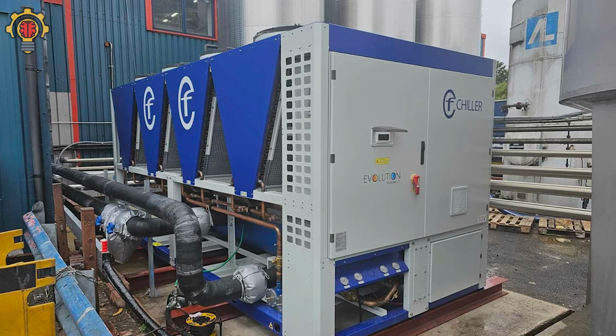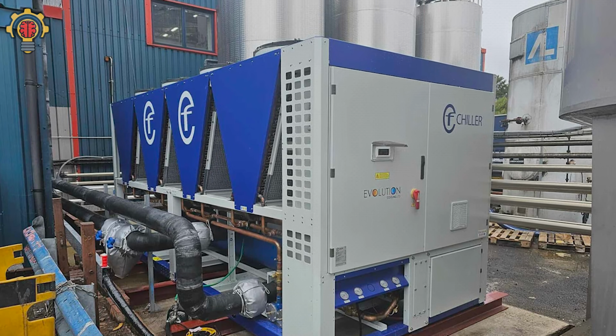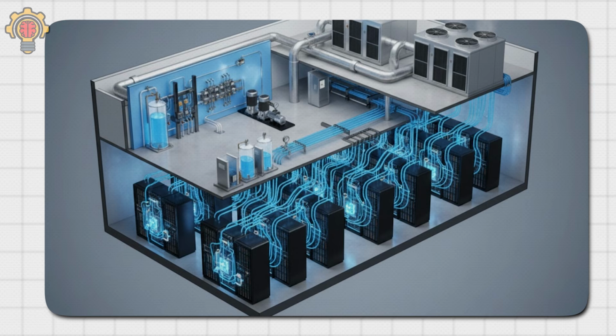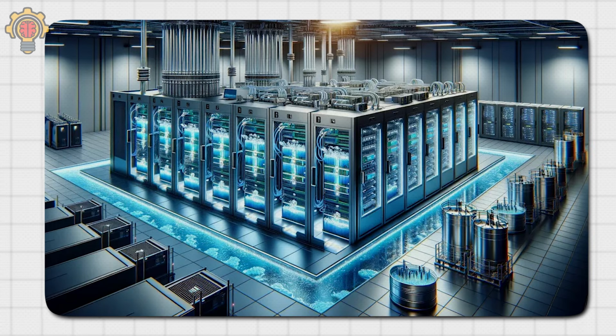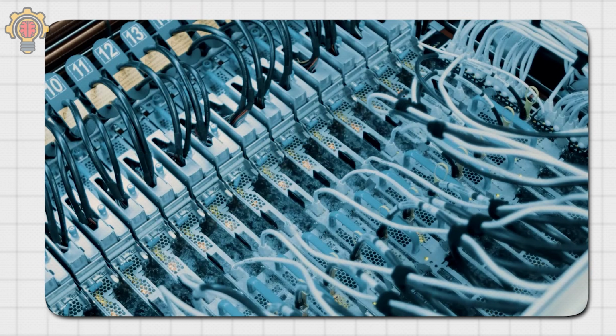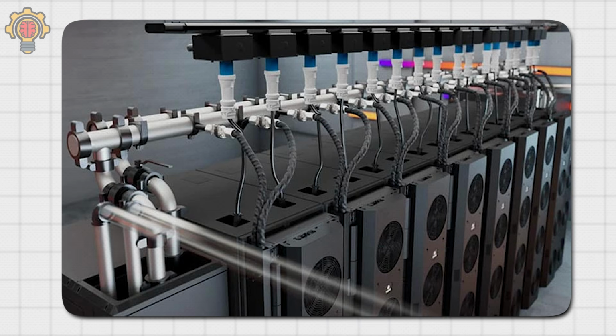Other systems place cooling coils directly inside the racks themselves. And then there is immersion cooling, one of the most futuristic technologies being developed today. Instead of using airflow, entire servers are submerged inside specially engineered dielectric liquids. These fluids do not conduct electricity, allowing electronics to operate safely while heat transfers directly into the liquid. No massive airflow systems, no giant fan walls, just direct liquid heat transfer.